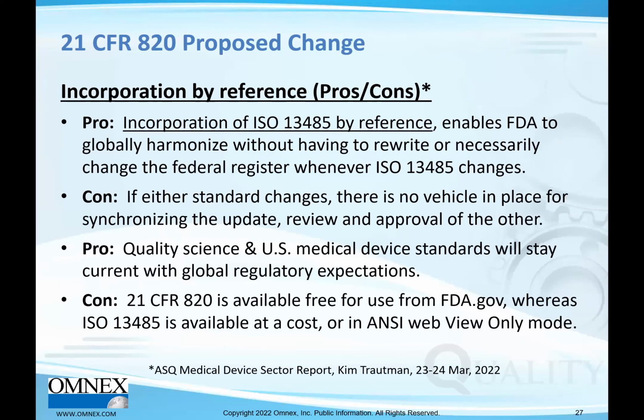So let's go back to the incorporation by reference, pros and cons. The pros of incorporation of ISO 13485 by reference: it enables the FDA to globally harmonize without having to rewrite or necessarily change the Federal Register whenever 13485 changes are made. The flip side, or the con, is that if either standard changes, 13485 or FDA for some reason wants to make a change, it doesn't automatically change the other. So synchronizing the updates, review, and approval of either or both standards, there's not a vehicle to do that that will change both standards. So that's going to have to be worked out. And what that means, how that's going to be done, I haven't heard anything yet.